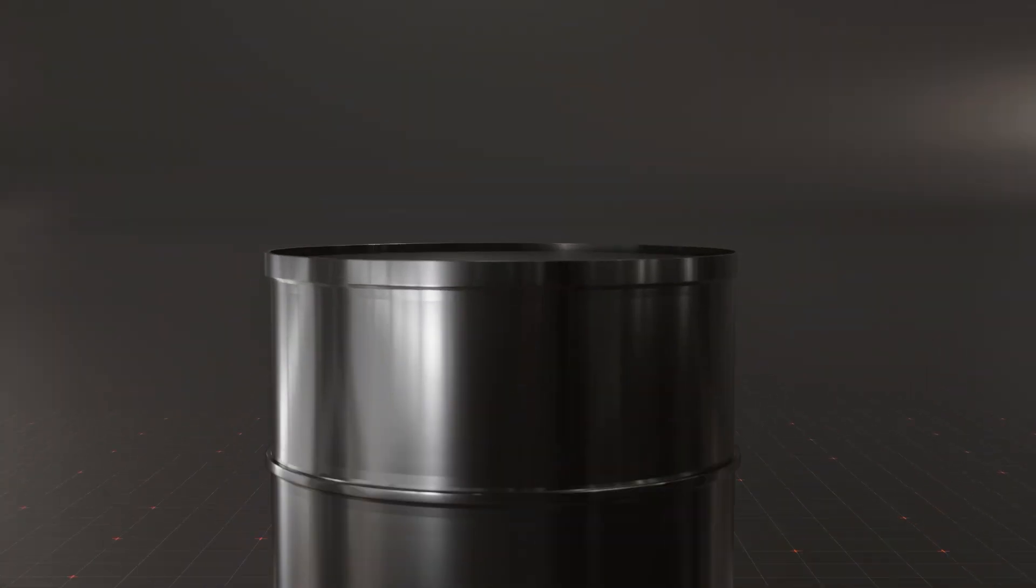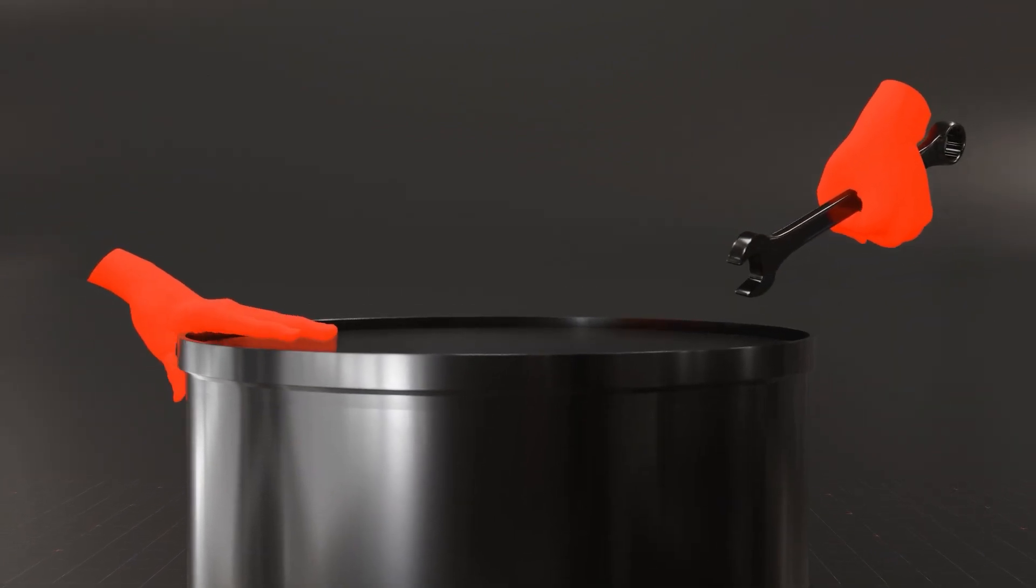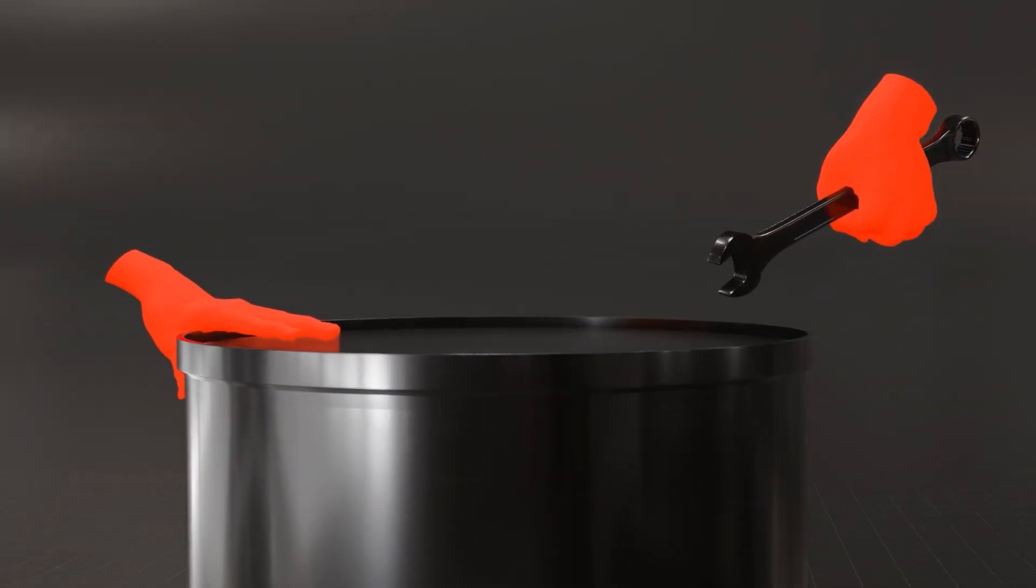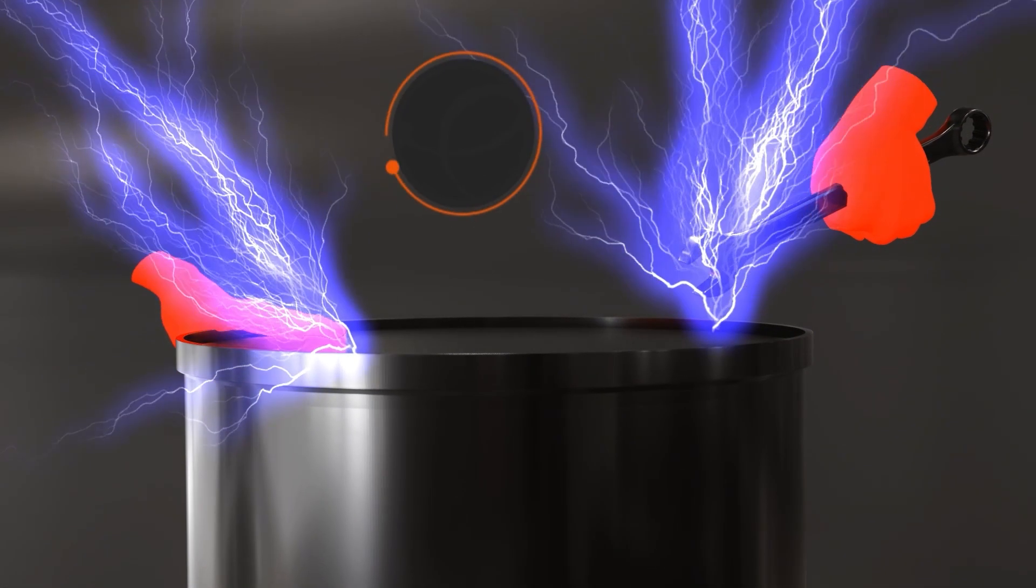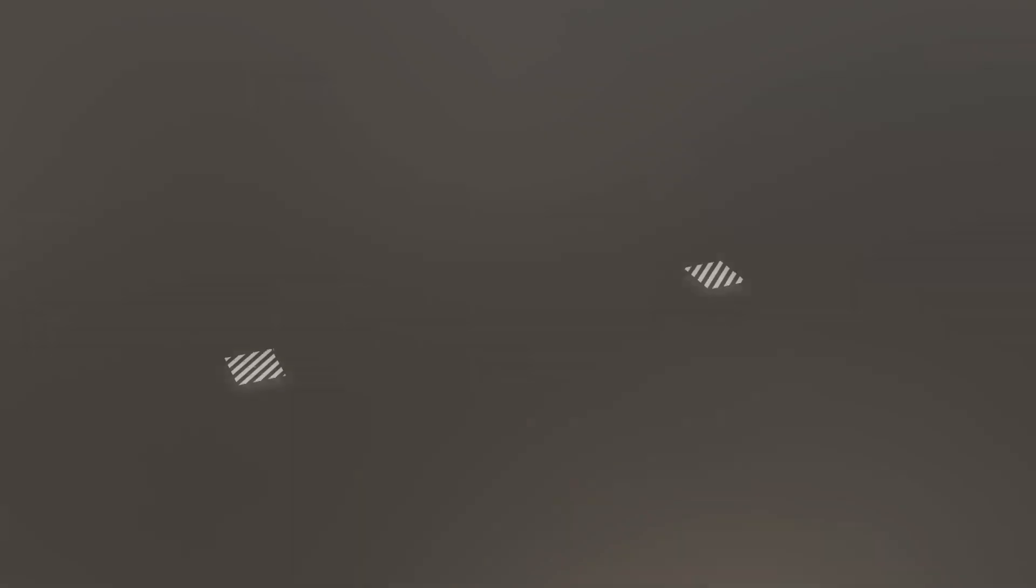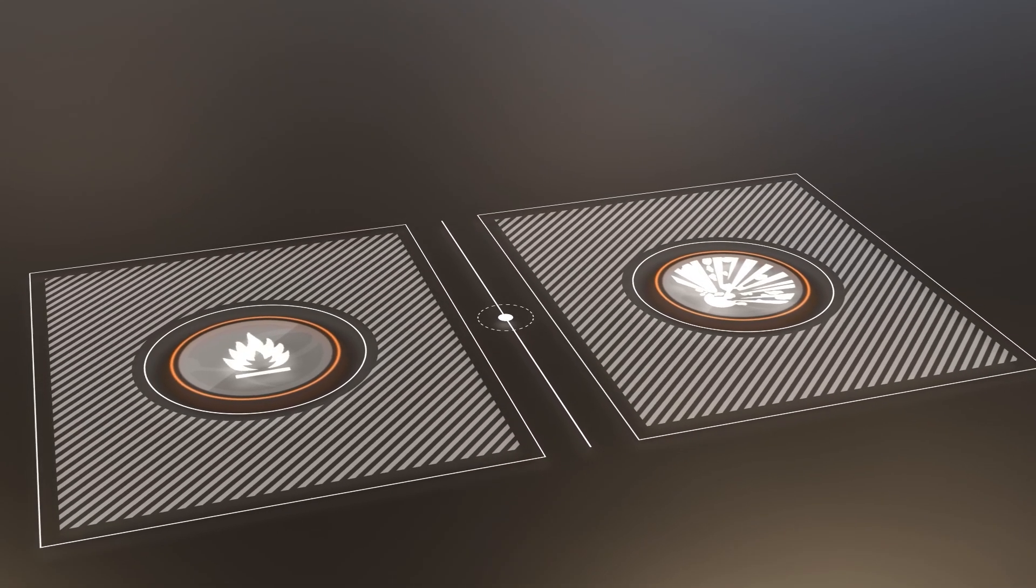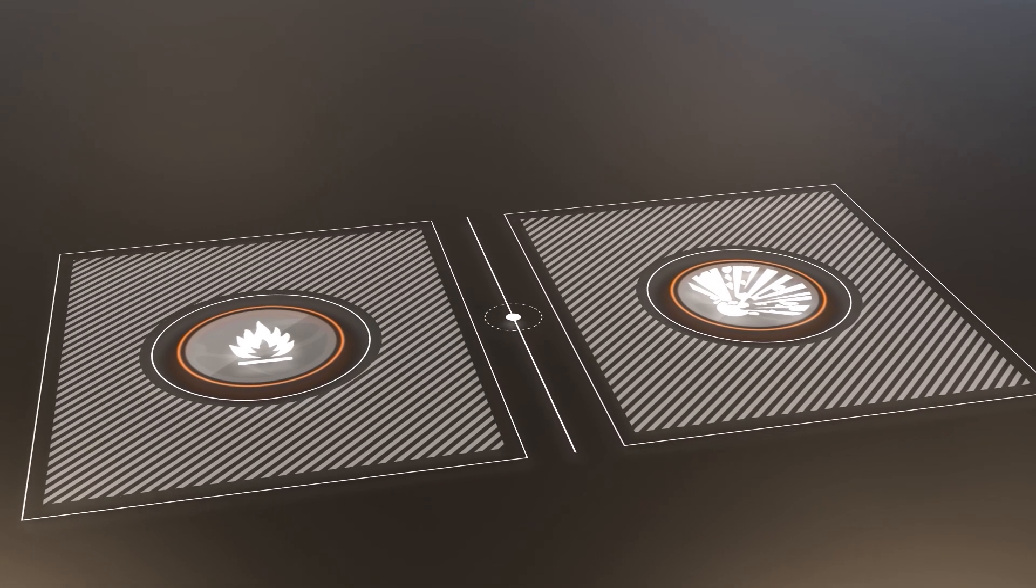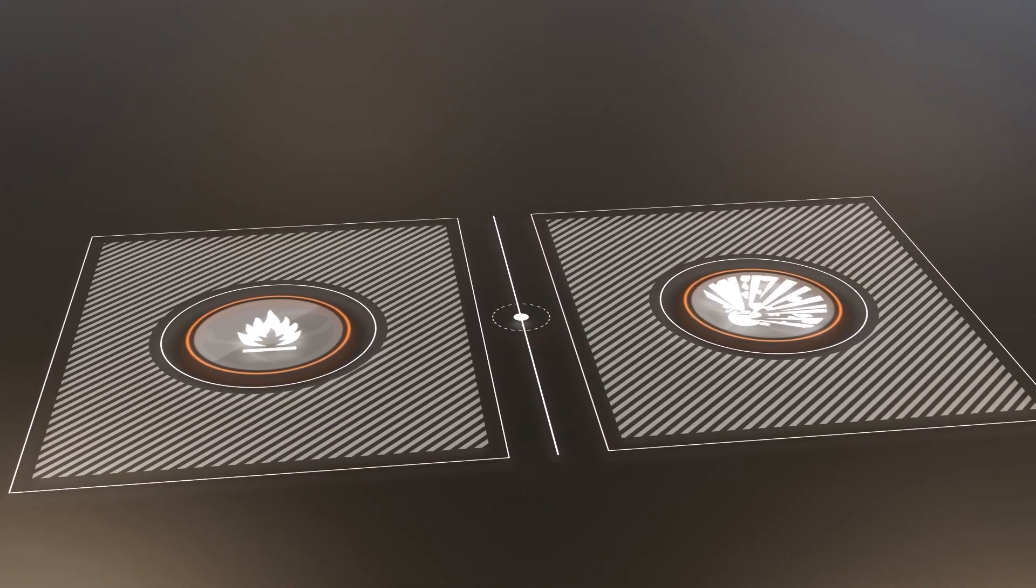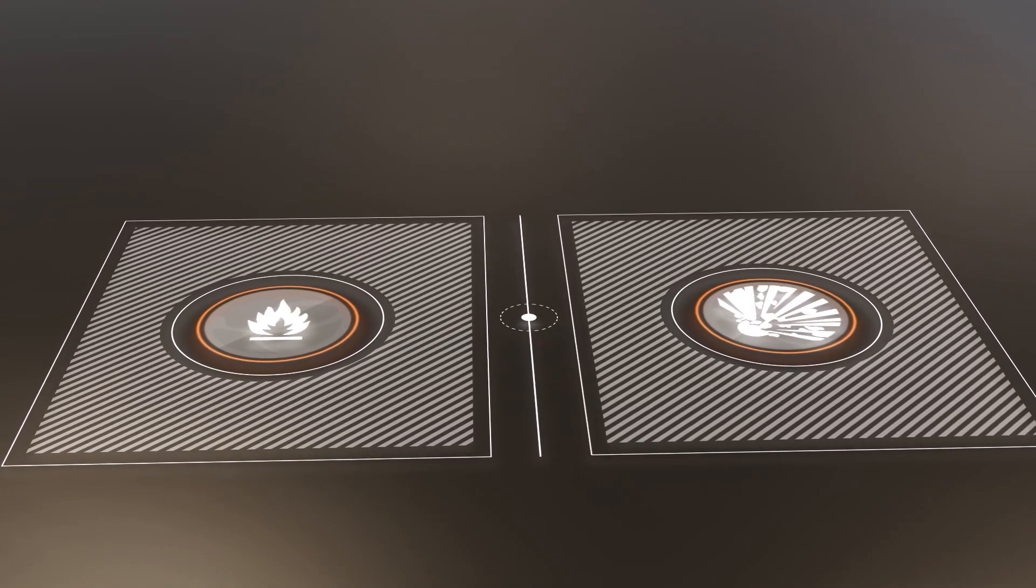If a container hasn't been correctly earthed, bringing a conductive object close to it, such as a spanner, or even touching the container with your hand, could cause a spark. Should this occur in a flammable or explosive atmosphere where fuel and oxygen are present and in the right concentrations, this sudden electrostatic discharge can lead to a spark, completing the fire triangle and leading to a fire or even worse.